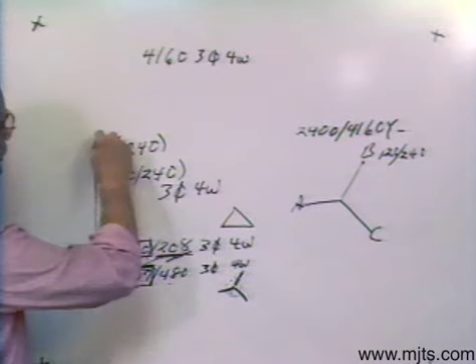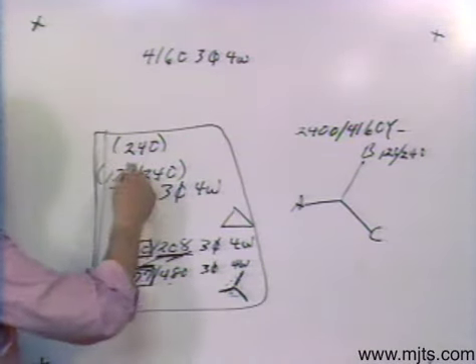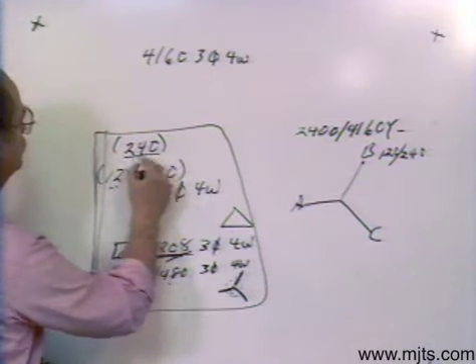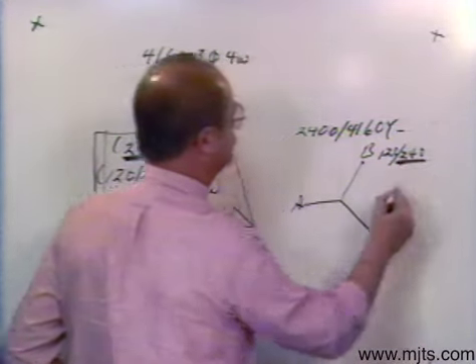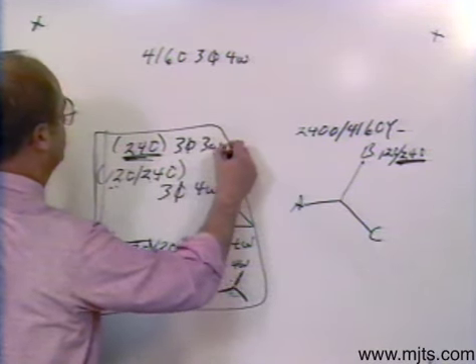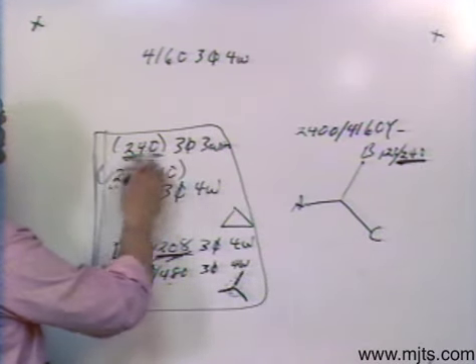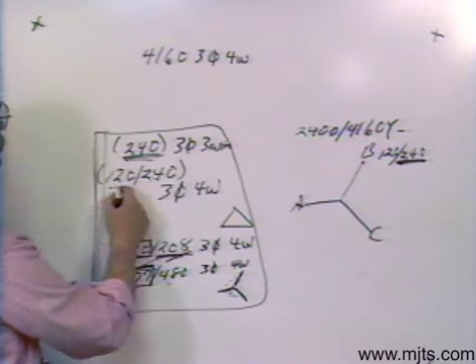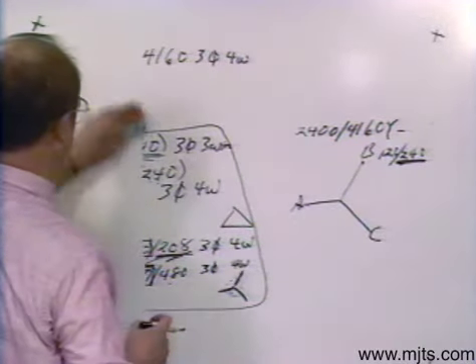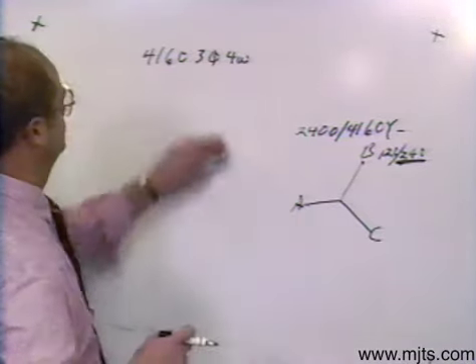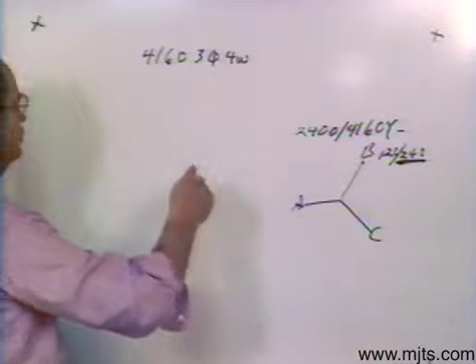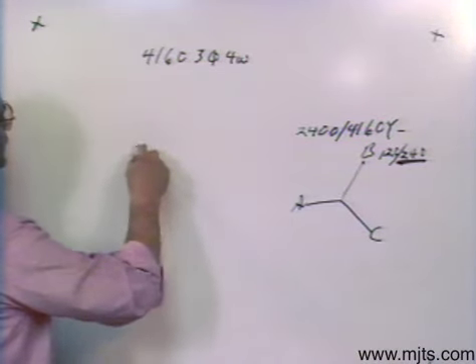So this is what you have to be concerned about when you make the low side connection — whether it's a 1-to-1.73 relationship or a 1-to-2 relationship. If I use the 240-volt rating and I want 3-phase, 3-wire — in other words, power load only — then it's going to be a delta connection. If it's 1 to 2, it's going to be delta.